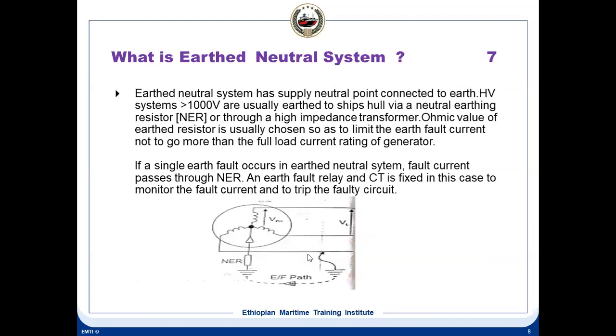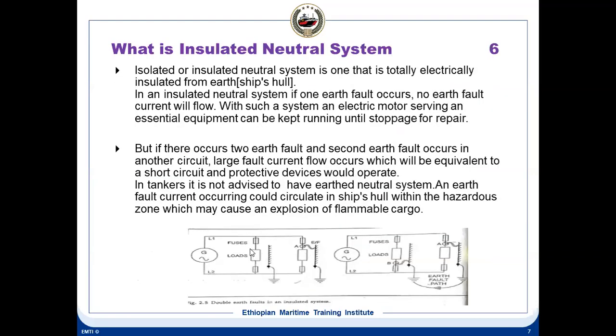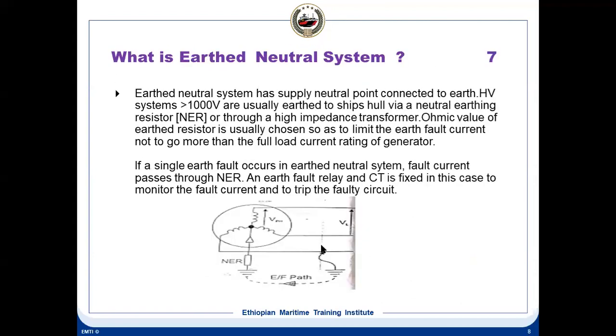So this is the earth neutral system, and this is the insulated neutral system. Here it's showing two circuits. Now here you see there's a fault current. Earth fault current is flowing from this system, but nothing happens. But if you have two earth faults, suppose this is also ground, then between these two phases there will be a path followed. The earth fault path is followed, and this is like a short circuit of the two phases, suppose they are two different phases. So this is an earth neutral system, and this is a neutral isolated system.